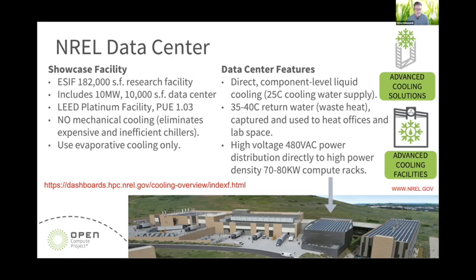I've been at the lab for 19 years, and we started planning our new HPC data center back in 2009; it was commissioned in 2012. It's a showcase research facility, with the data center sitting between office space to the right and laboratory space to the left. It has usable, raised, uninterrupted floor space of 10,000 square feet, and is capable of supporting 10 megawatts of IT load. It was a LEED Platinum facility overall, including the data center. We had a design target PUE of 1.06 or better. Our trailing 12-month PUE is about 1.03 - I checked, it was 1.026 - but at some point you get to diminishing returns.